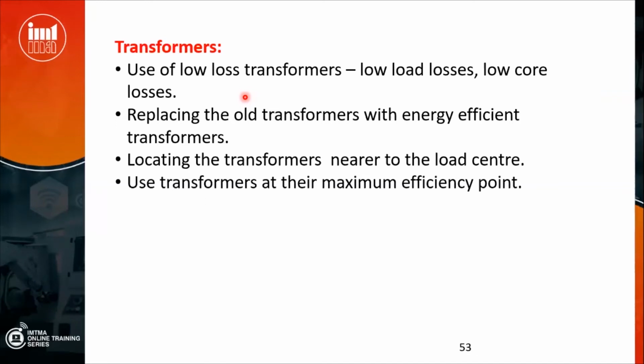Generally, distribution transformers are not switched off. Power transformers are in the power system, in large receiving stations and generating stations. In distribution transformers, generally the highest efficiency takes place at around 70% load. Even roadside distribution transformers are designed for a much higher load to have the highest efficiency, because when the load changes, they cannot be switched off anyway. All 24 hours they have to be in service.